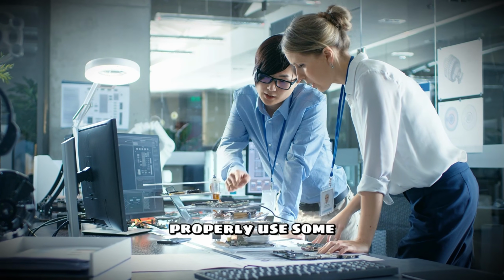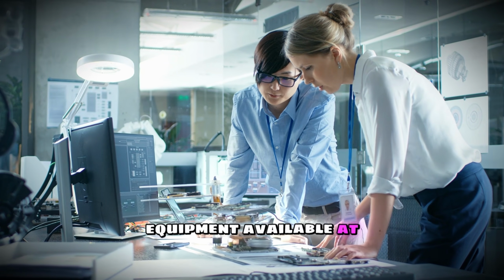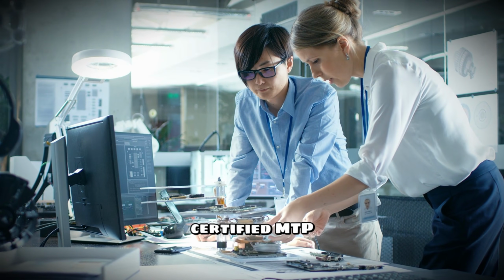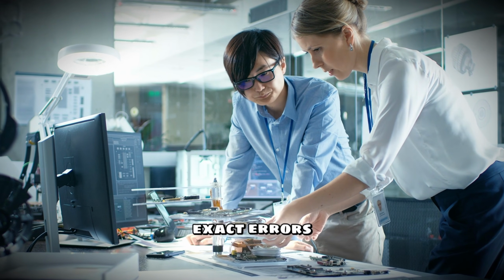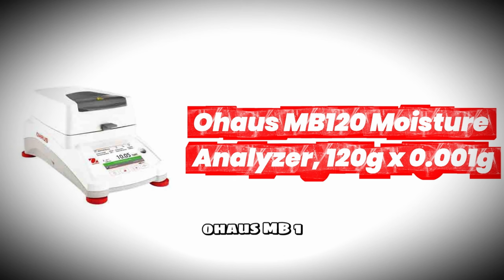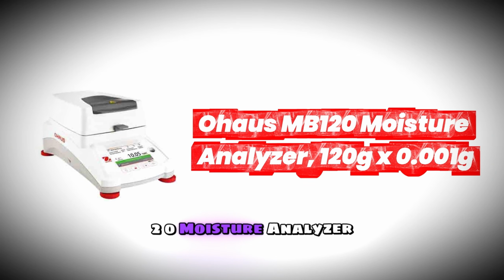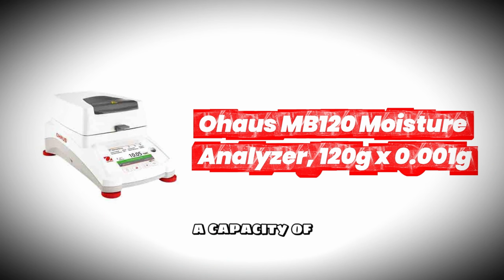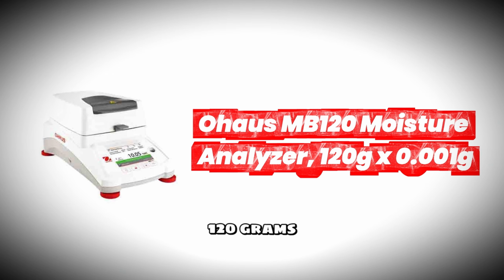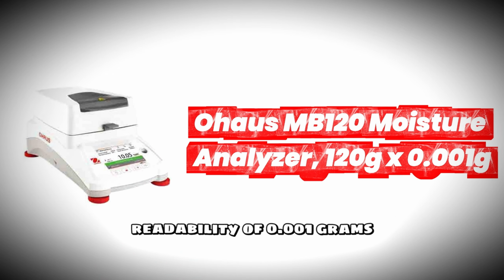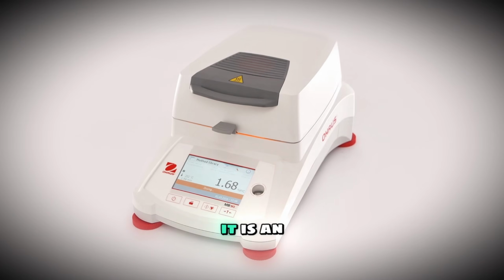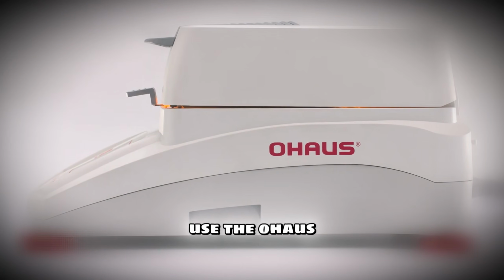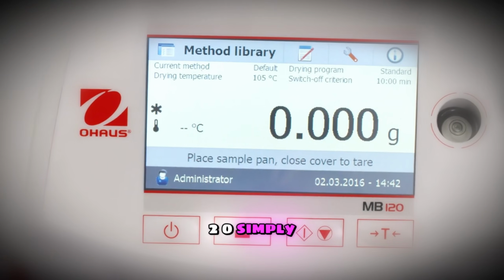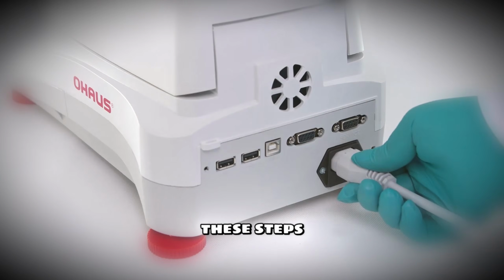Let us look at how to properly use some of the top-tier equipment available at Certified MTP to avoid these exact errors, starting with the MB120 Moisture Analyzer. This unit offers a capacity of 120 grams with an impressive readability of 0.001 grams. It is an absolute powerhouse for testing construction materials. To use the MB120 simply and effectively, follow these steps.